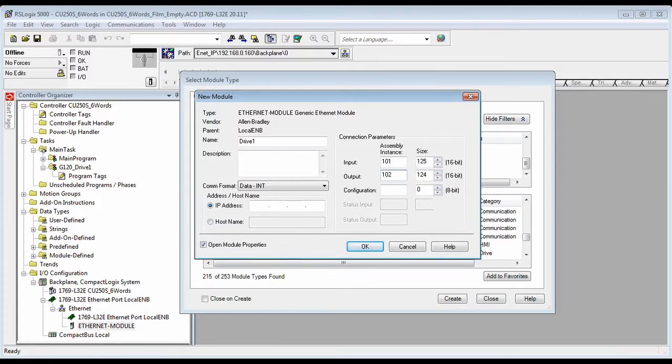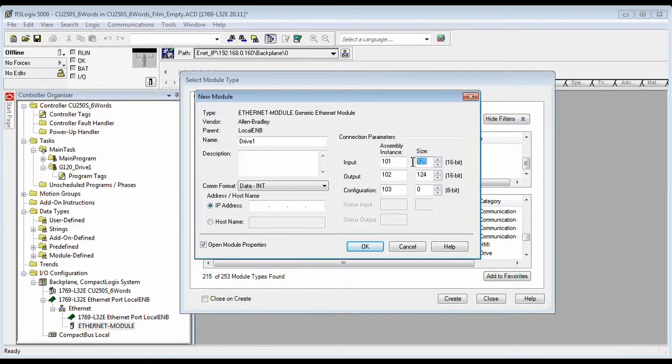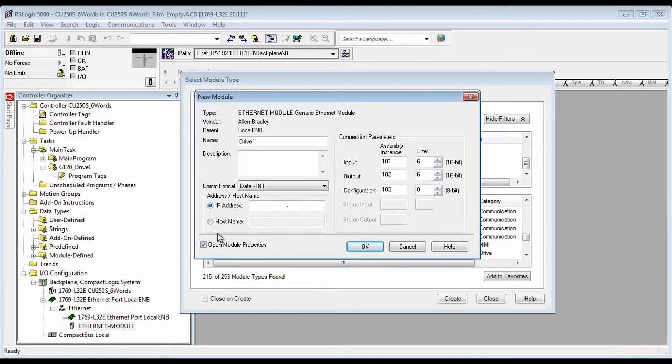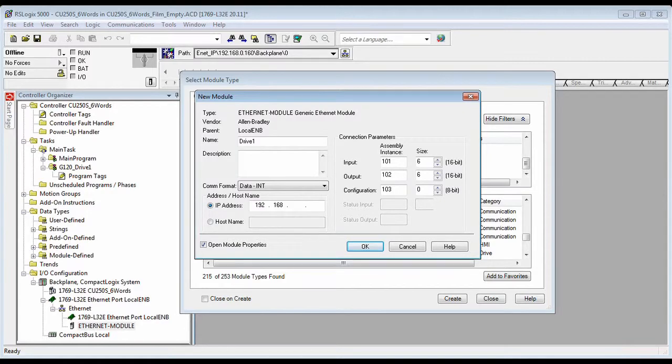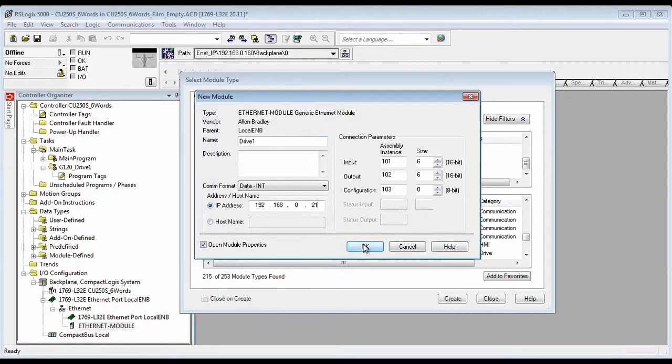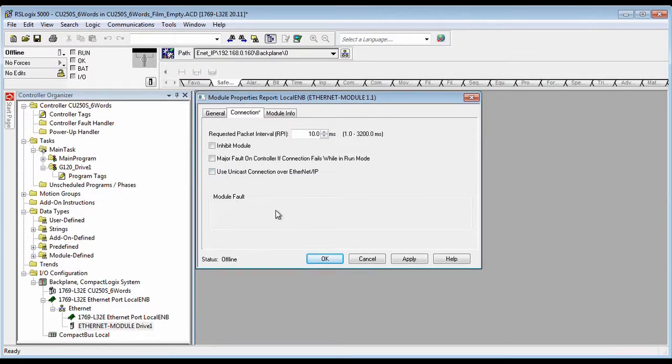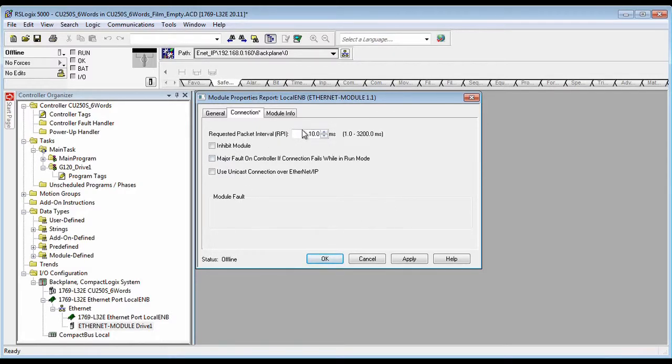These are the standard input instance numbers, 6 words in, 6 words out, no configuration words. Give it the IP address of the drive that you've set, multicast, whatever update time works well for your application.